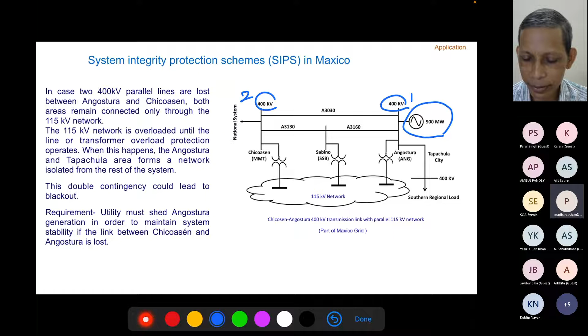Real world applications on the control system perspective are called system integrity protection schemes, to maintain the integrity of the system. In Mexico, there are two stations with 400 kV lines, station 1 and station 2, which have hydro plants of around 900 megawatts. If this double circuit 400 kV line trips, there is a path on the 115 kV line which pushes power instead, but this path is very lengthy with high impedance.